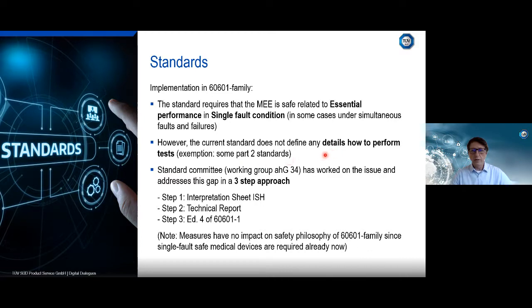Some Part 2 standards do address this. For instance, the dialysis machine standard has defined requirements for how such single fault safety with respect to essential performance has to be implemented. However, this is not the case for all Part 2 standards. The standard committee has noted this gap, and the ad hoc group 34 has worked on the issue, addressing it with a 3-step approach. They have now published, or it will be published in November, an interpretation sheet on how to handle this issue. They want to publish a technical report as step 2, and step 3 will be the 4th edition of the standard, which will then include all these requirements, which we will see in a few seconds.